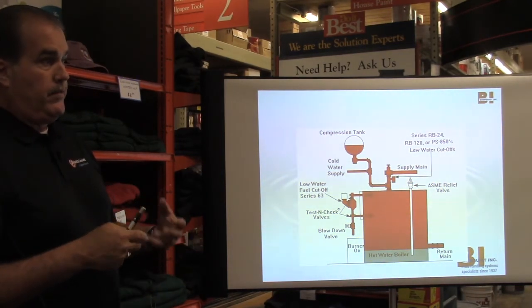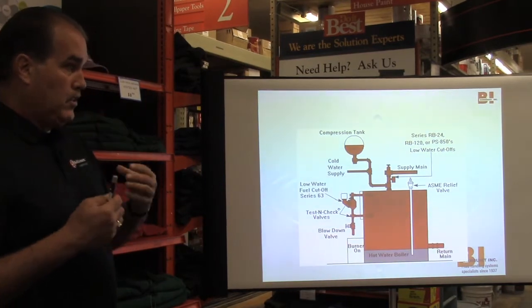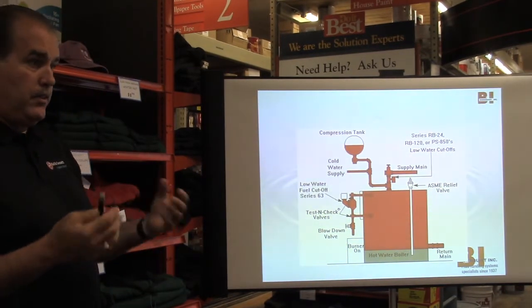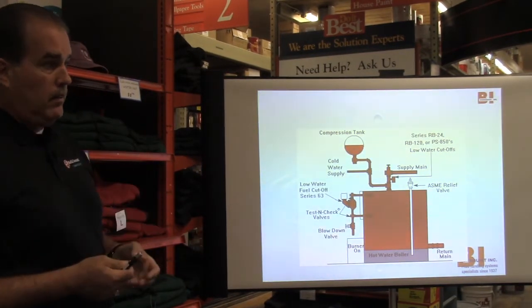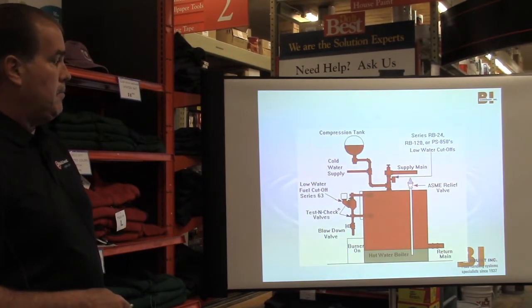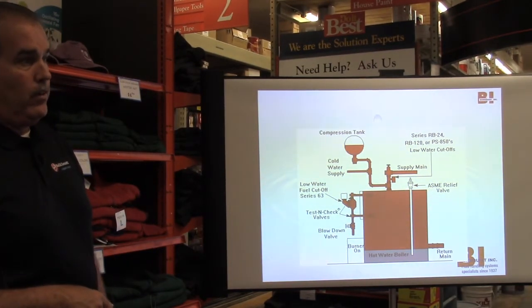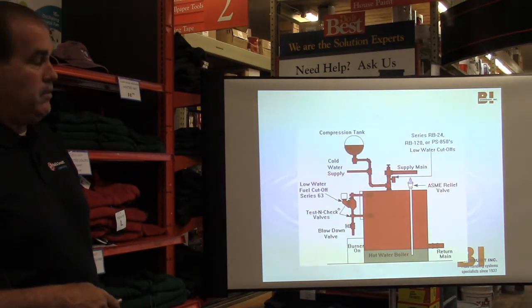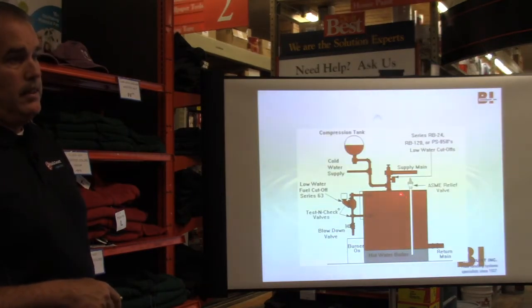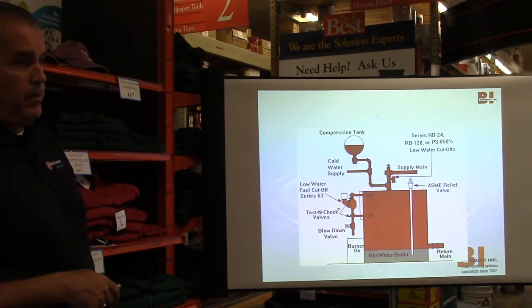Basically what happens is, if the system for some reason gets overpressured, before you start leaking through your pipes or blowing radiators or whatever, this guy will pop and dump the water out onto the floor or down a drain. That's what he's for. He's a safety device designed to relieve pressure in the boiler.